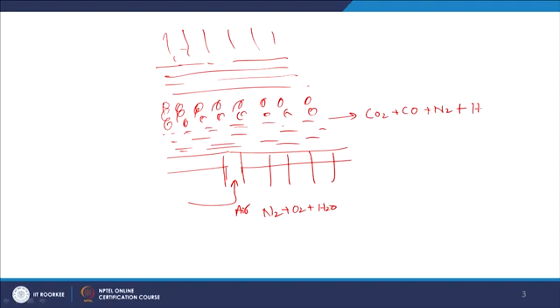Now this gas moves through the green coal. This is the main coal, and feeding of green coal to the grate is continuous. When the gas goes through the green coal, it helps in driving the volatile material out of it. In fact, the coal ignites somewhere between the green coal and the incandescent coke, somewhere here. Ignition takes place here, but you can see the flame at the top. Secondary air is provided from here for the proper burning of the gases, because there is incomplete combustion also. So the carbon monoxide, in the presence of secondary air, is also converted into carbon dioxide.